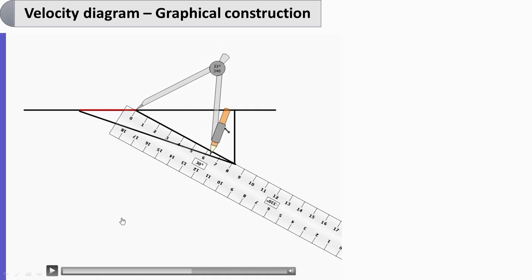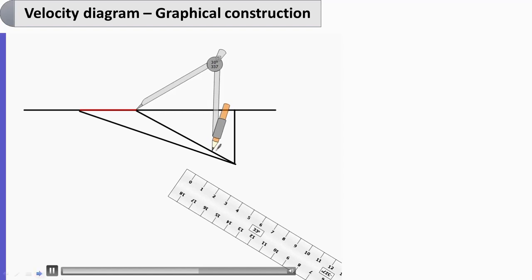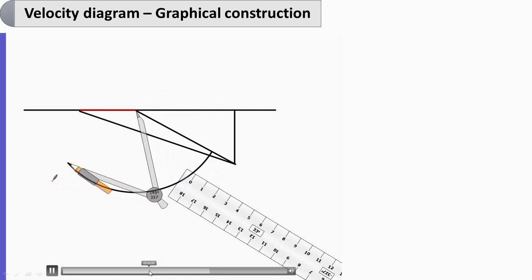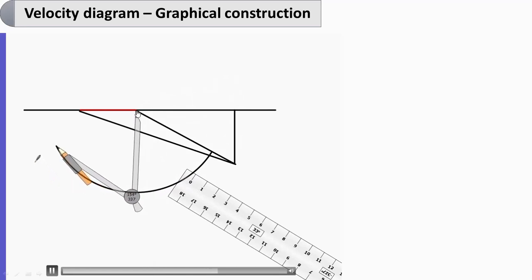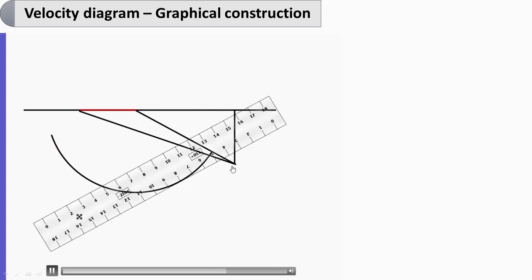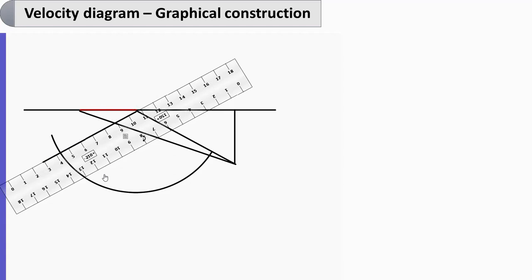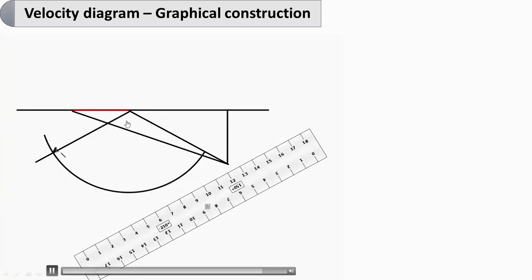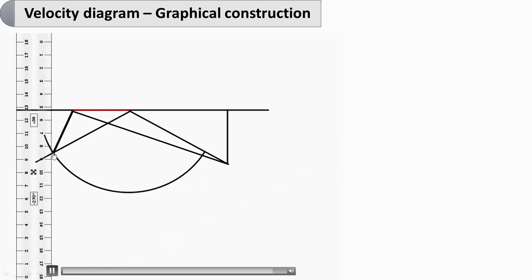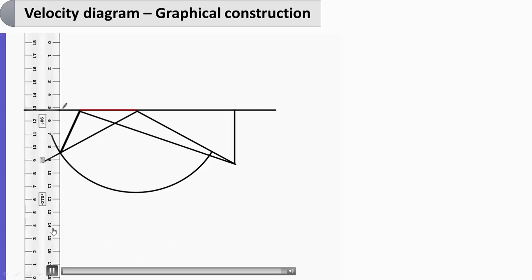Now Vr2 is 0.8 times Vr1. Reading from the scale, Vr1 is nearly 8.3 centimeter; multiply by 0.8 to get 6.5 centimeter. Take 6.5 and draw an arc of 6.5 from this point representing Vr2. Since beta1 is measured as 30 degree, beta2 is also 30 degree. Join the intersection point and draw a vertical to complete the outlet triangle.